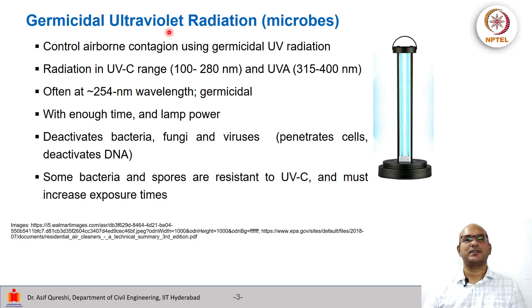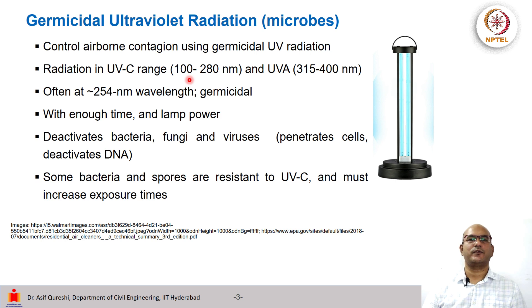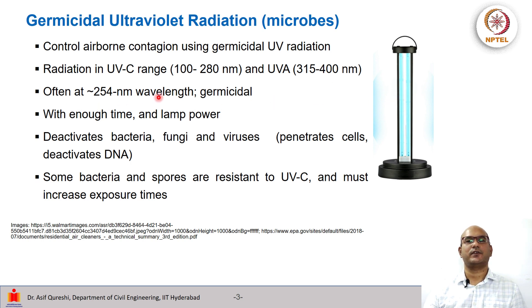Then we have germicidal UV radiation, which is essentially used to remove microbes. This is an example of a UV lamp, which emits radiation in the UV-C range or UV-A range. The UV-C range is 100 to 280 nanometers, and the UV-A range is 315 to 400 nanometers. Often these lamps operate at around 254 nanometers, at which wavelength the rays are germicidal.